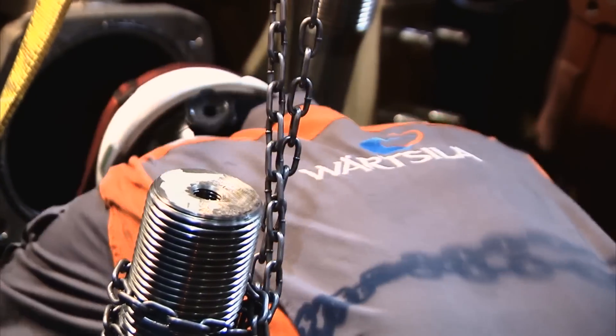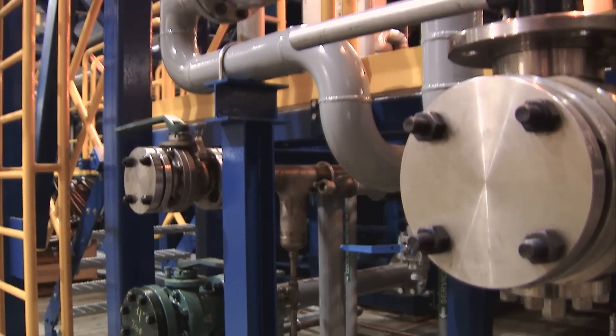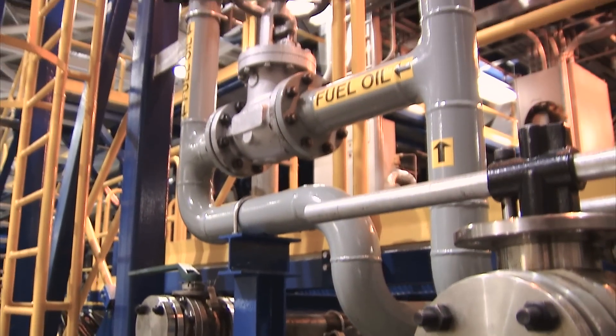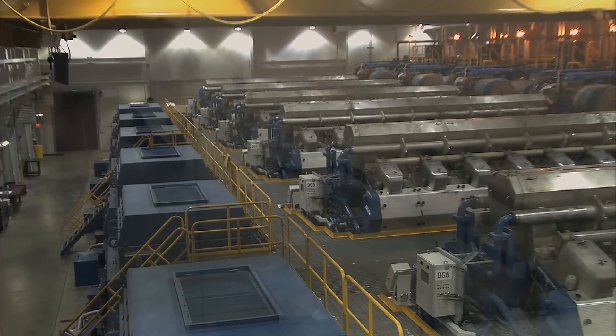The reason for the selection of smaller reciprocating engines was to add inertia to the system that we knew was lacking with the smaller gas turbines, and to support long-term sales to fellow utilities who will need this kind of load-following support.